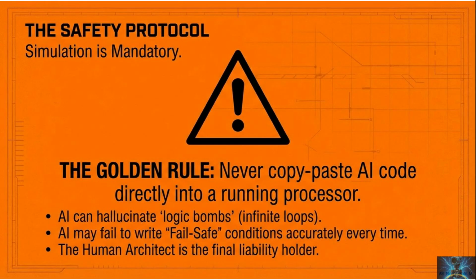The safety protocol. Simulation is mandatory. This is non-negotiable. Never copy and paste AI-generated logic directly into a running processor. AI can produce logic that compiles but behaves dangerously, including runaway loops, improper latching behavior, or missing fail-safe actions. The safety protocol is simple. Generate, review, simulate, test in a virtual environment, and only then deploy.